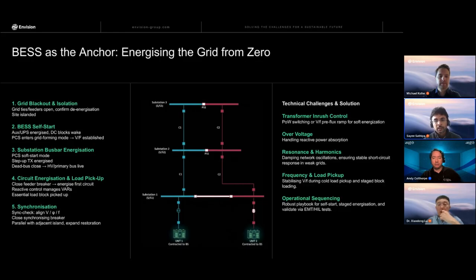So the first risk is obviously the transformer inrush current limit. So, current limitation: we have the soft start capability on the PCS, so that we ramp the voltage from 0 to the nominal in a slow method, so that we can limit the inrush current of the transformer. And we also have super grid transformers on the substation side. So basically we can use the point-on-wave switching device to close the breakers when there is zero current.